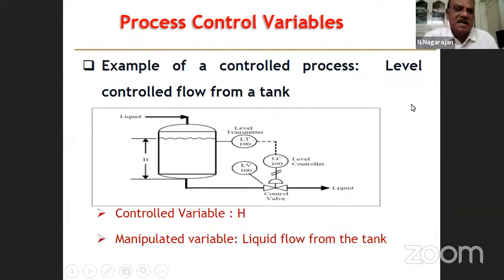Here we see the same tank system in a controlled environment. We have this tank which is covered and the liquid is coming in, the head is developed here. There is a level measuring mechanism here, level transmitter. So that is measuring the level, and the control signal from the measurement is acting on a control valve. So level control valve. This is called level controller. Level transmitter is the measuring device. And the final control element is a control valve. If the level is more, it may ask the valve to open more and allow more flow.